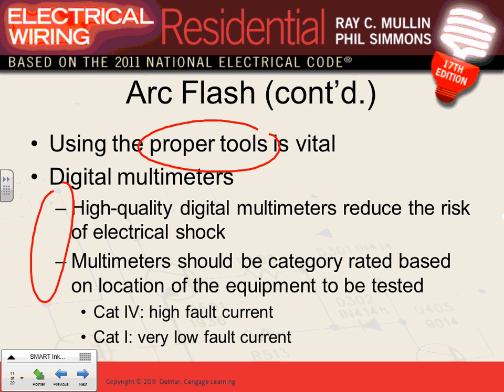There are two categories for your employees: high fault current and very low fault current meters. Why is high fault current good? Because if you have a fault while holding the meter, it won't explode in your face.